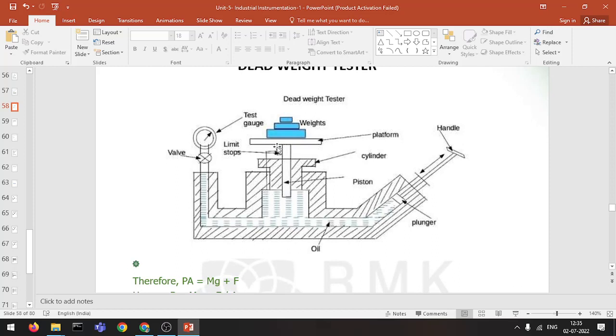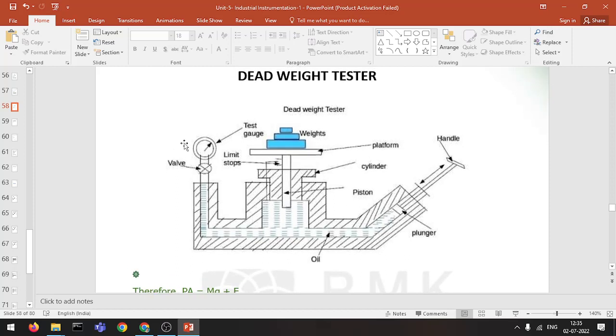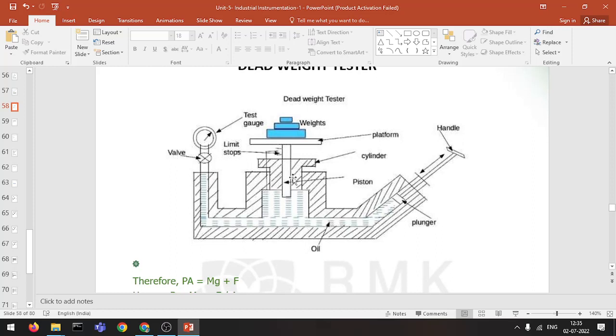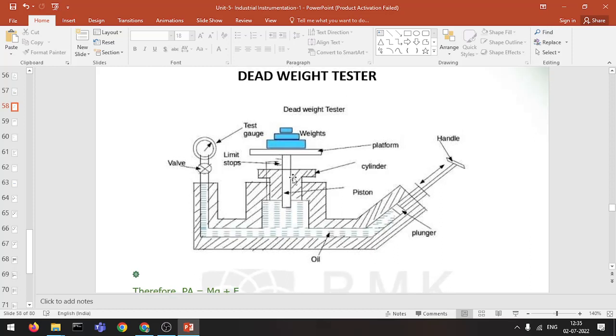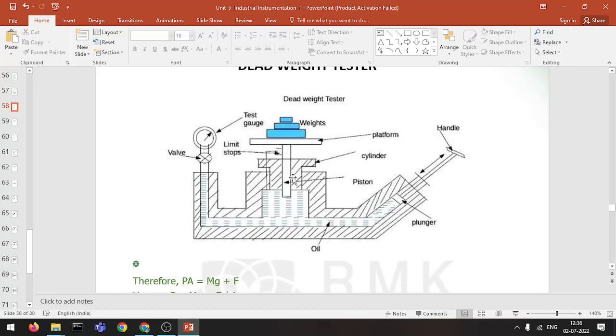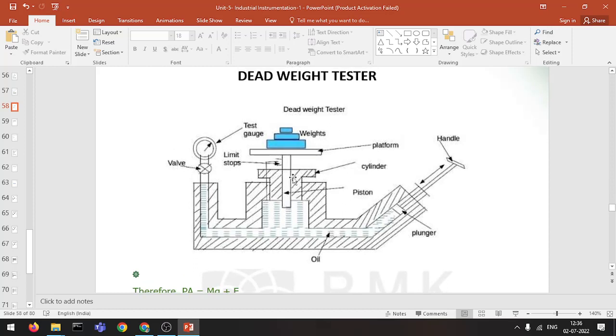The advantages of this type are that it is simple in construction and easy to use, and it can be used to calibrate a wide range of pressure measuring devices. Applications: this can be used to calibrate all kinds of pressure gauges such as industrial pressure gauges and pressure transmitters. Limitations: the accuracy of the dead weight tester is affected due to the friction between the piston and the cylinder and due to the uncertainty of the gravitational constant g.